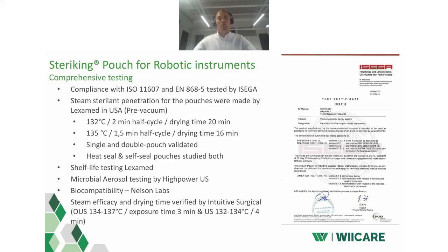And it was done in the so-called half cycle, where the holding time in the sterilization is cut in half from the minimum holding time mentioned in the standard. So in this half of the time, the steam that goes into the pouch needs to kill the microbes and spores on the instruments. And it did, of course. And we validated for single pouch use and for double pouch use. So this half cycle was working even if we do double pouching. Steam will go into the pouch. It will kill the microbes and spores, even in this worst case scenario, like half cycle. We studied this, of course, for heat seal and self-seal pouches both.